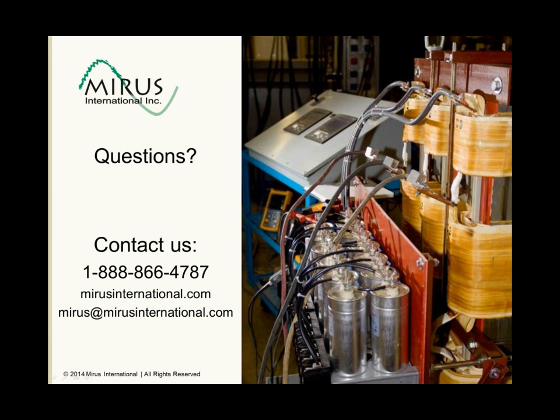One situation where we've seen it be an issue is under backup conditions, where a generator is used for backup power and they leave all of the connected load, which the generator could not handle, supplied by the variable speed drives and harmonic filters. In those cases, we have to be careful to make sure that the generators can handle it.